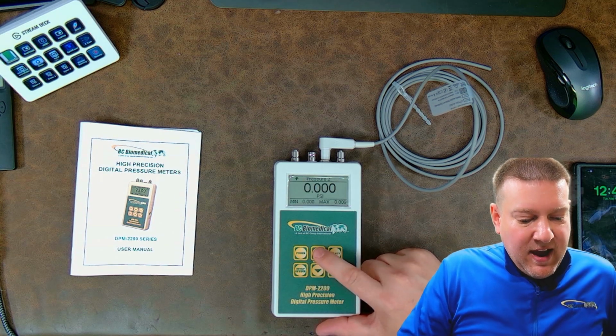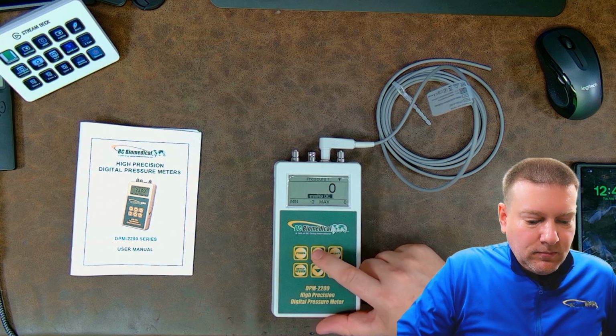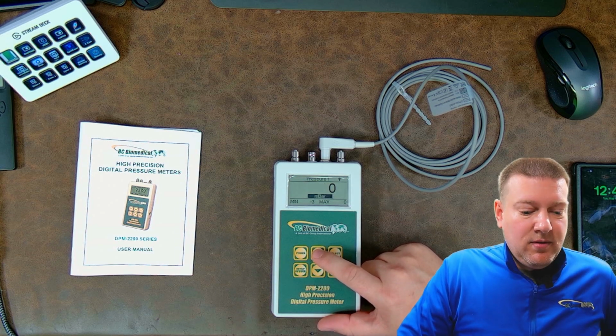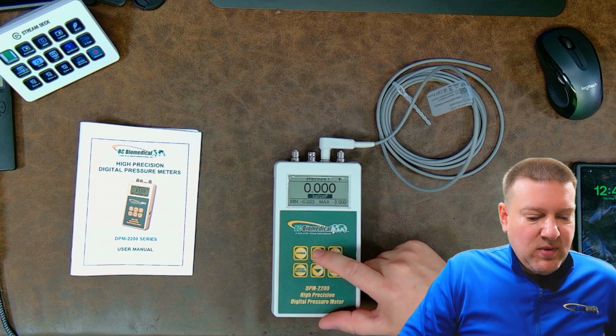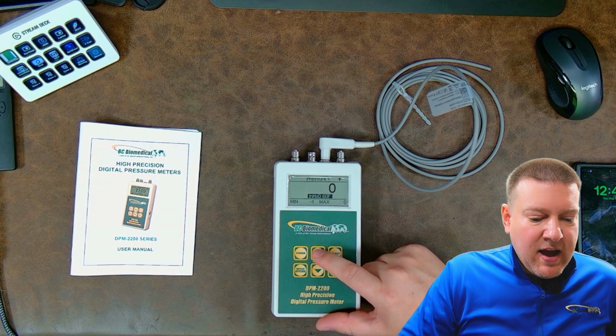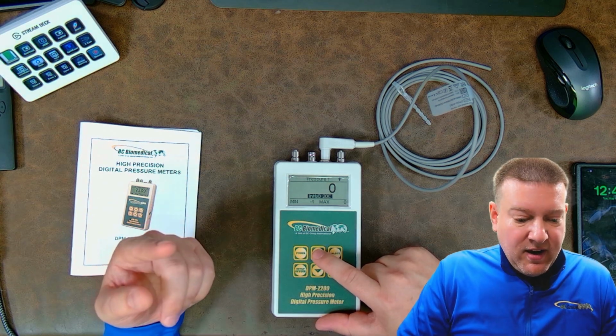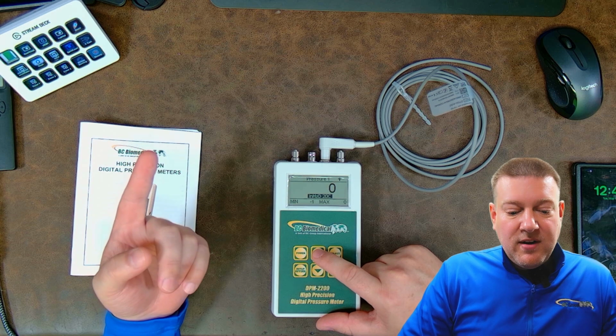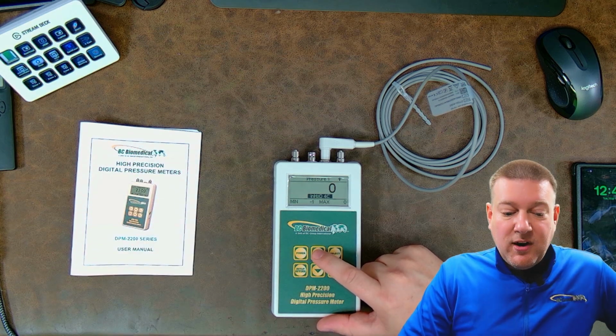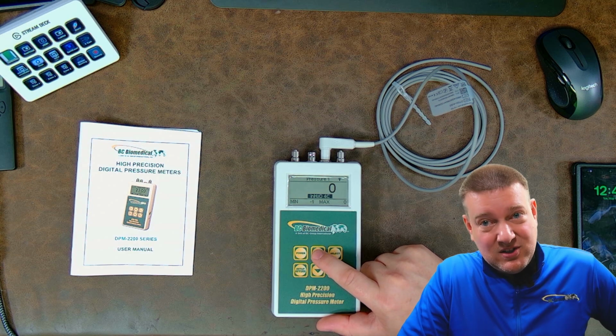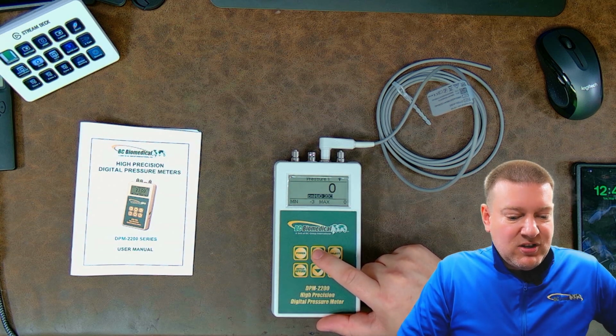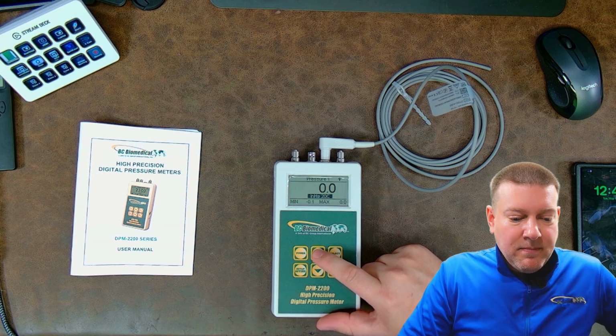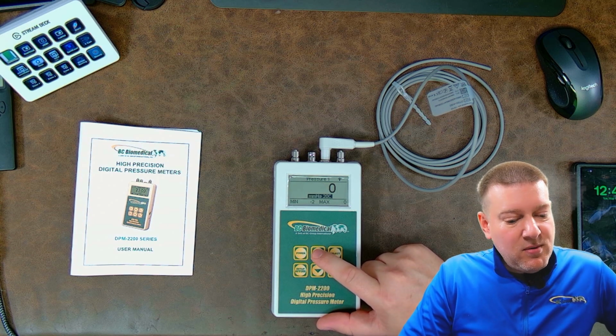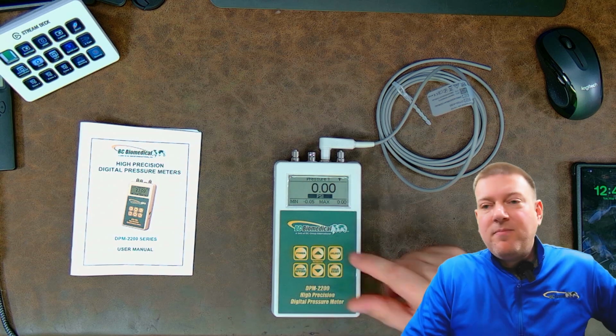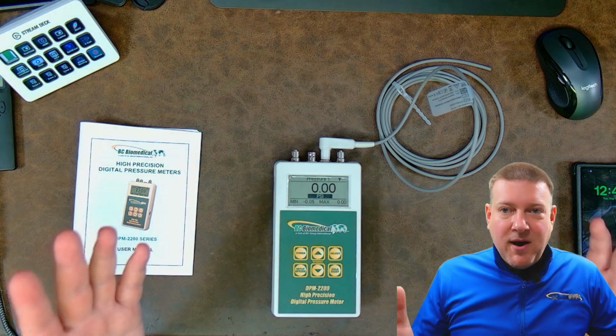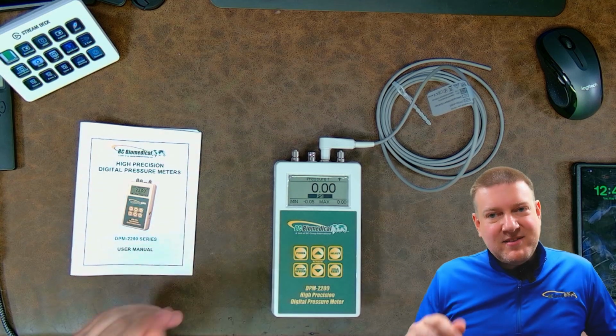Okay, so we have PSI, millimeters of mercury. We have bar, millibar, kilopascals. We've got kilograms per centimeter squared. I have inches of mercury, again, at 60 degrees Fahrenheit. We have inches of water at 20 degrees centigrade, inches of water at 4 degrees centigrade. Of course, water's density also changes according to temperature. We have centimeters of H2O at 20 degrees. We have inches of mercury at 20, inches of mercury at 0, millimeters of mercury at 20, millimeters of mercury at 0, and back to PSI. That's a lot of engineering units. But that way you don't have to do the calculations yourself. Just set it and forget it, right?